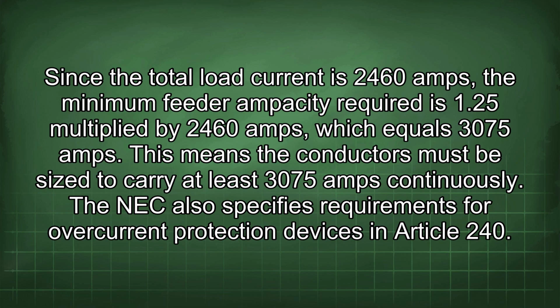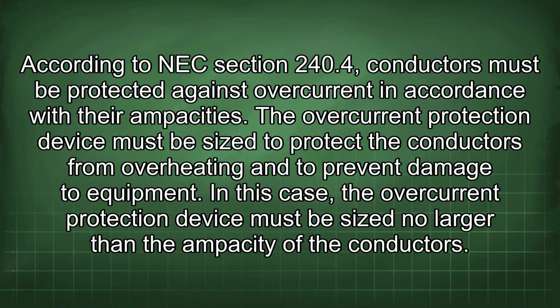The NEC also specifies requirements for overcurrent protection devices in Article 240. According to NEC Section 240.4, conductors must be protected against overcurrent in accordance with their ampacities. The overcurrent protection device must be sized to protect the conductors from overheating and to prevent damage to equipment. In this case, the overcurrent protection device must be sized no larger than the ampacity of the conductors.